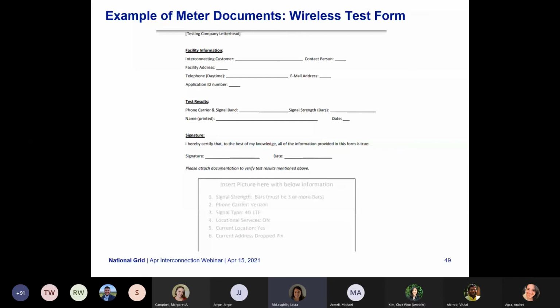So this is what we would need filled out. It would need to be on the testing company letterhead at the top, with the facility information and the test results. You'll need to ensure you had 3 bars or more, and it needs to be the 4G LTE Verizon carrier. You would also need the signature and date, as well as a picture from the site showing where the meter is going to be installed. So that's a little insight into that process and document. Again, not applicable for all projects, but if you're going with the wireless meter option, this would need to be filled out and sent in.